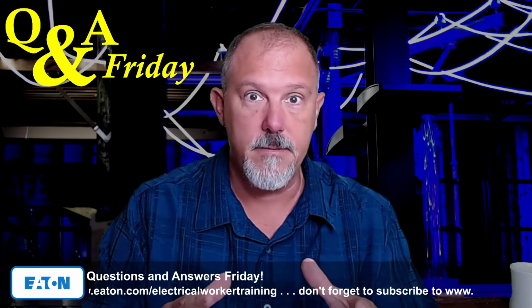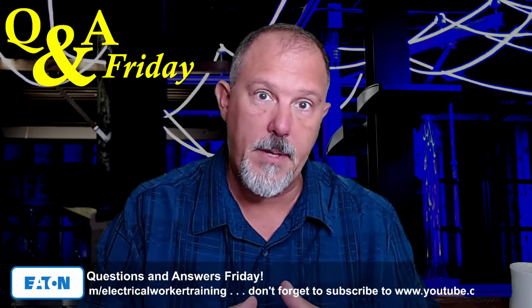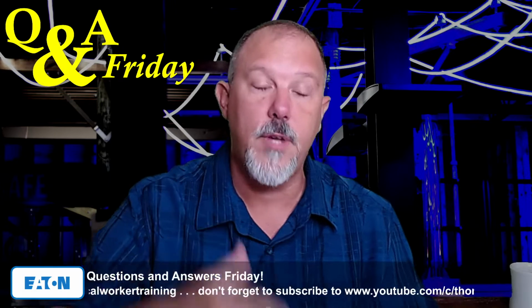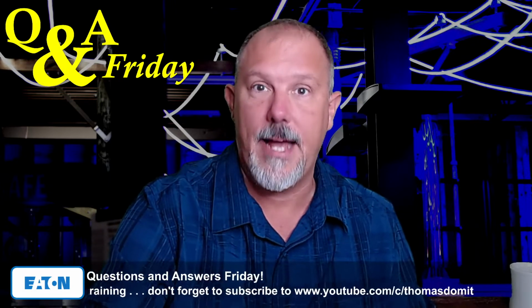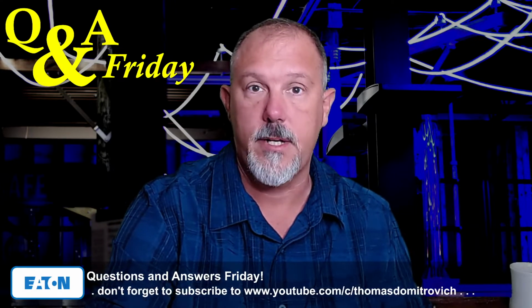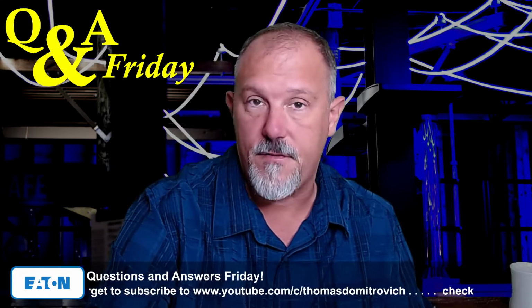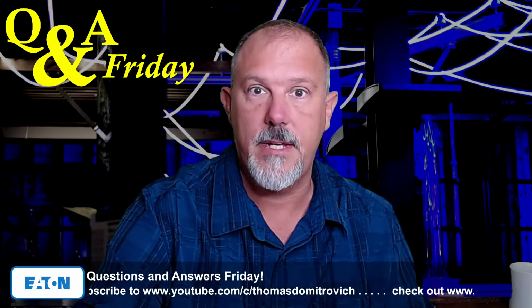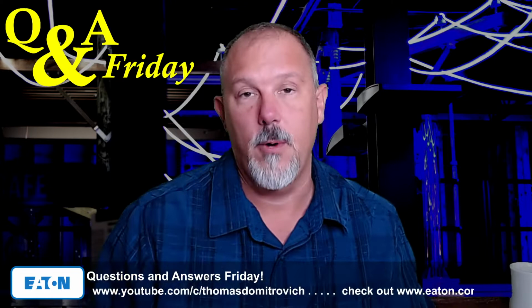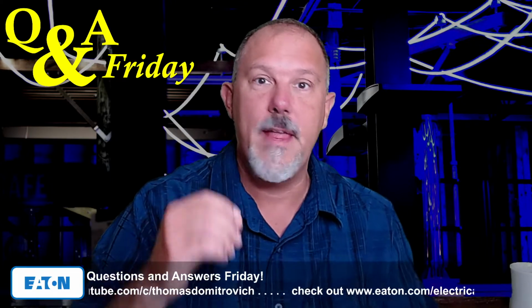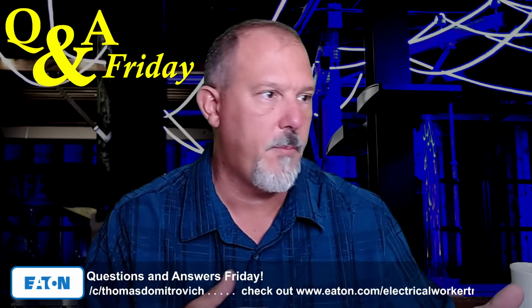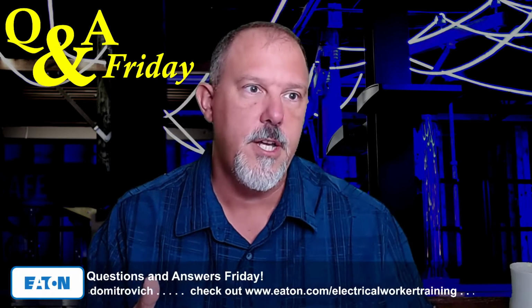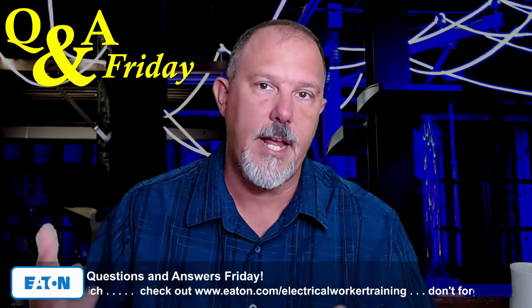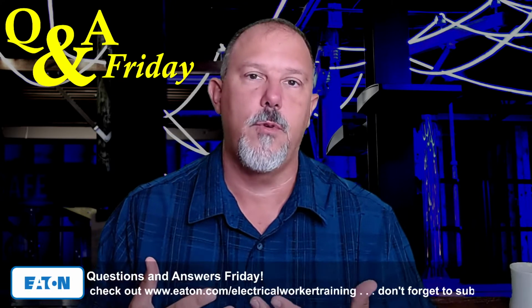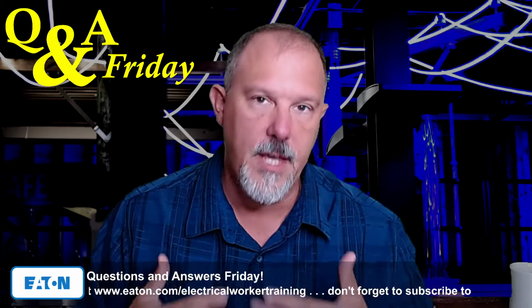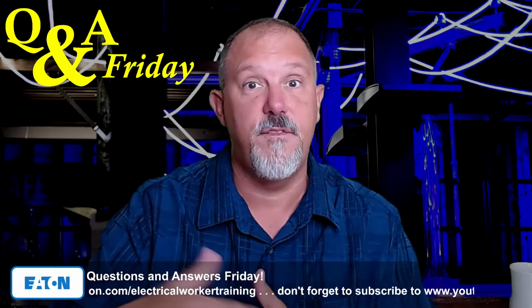If you think about it, you have to dress for the PPE. You have to have the proper PPE. You can't assume that it is actually in an electrically safe working condition until you verify it. And you have to assume that it is not in an electrically safe work condition. And that's the challenge on all of this, whether it be medium voltage or low voltage. When you have high incident energy values and you have to dress for it, if it's so high that you can't dress for it, then you have to have other methods to verify.